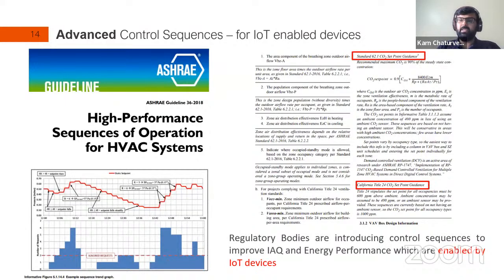And in that, you'd notice they have a requirement for zone level CO2 set point and zone level CO2 control. Providing that with a traditional BMS is very challenging, because a particular system would have multiple zones, and provisioning multiple zones requires a lot more IO points and wiring. But providing this with a wireless IoT BMS is way easier - not just providing the sensor and the data, but also communicating and applying this data would be way easier.